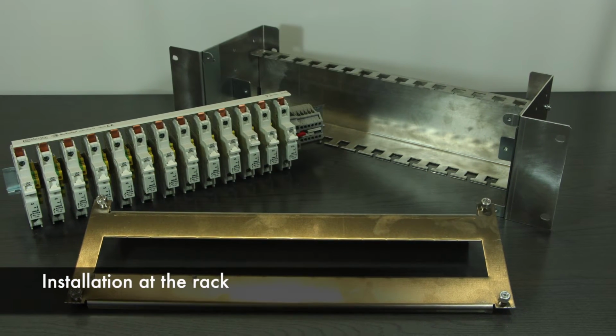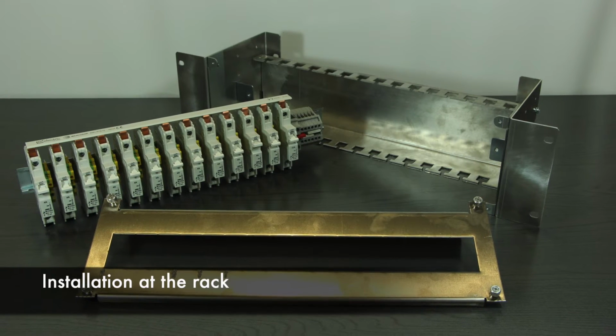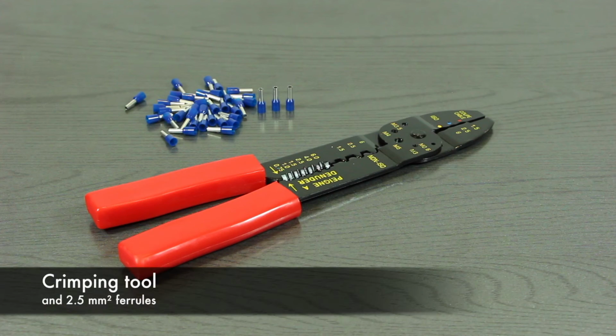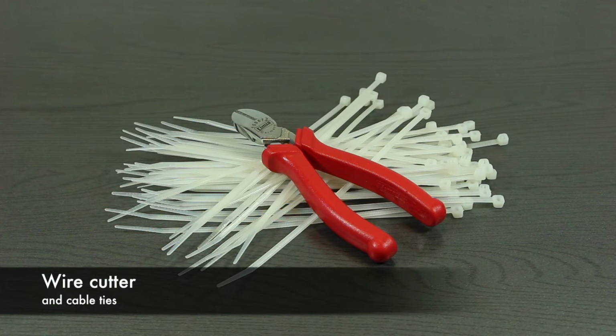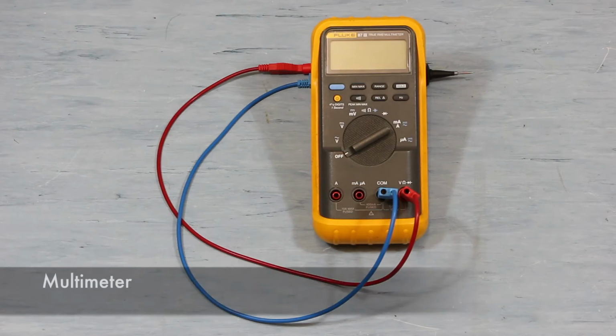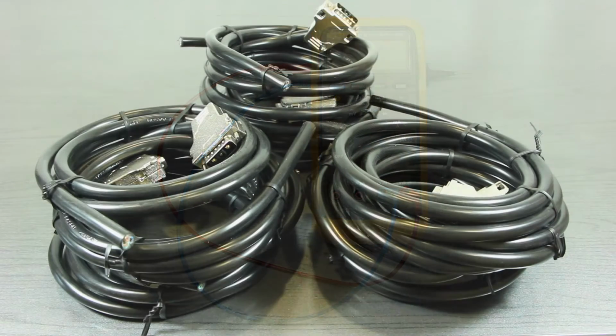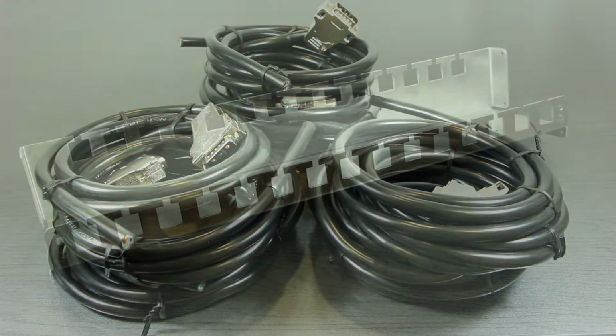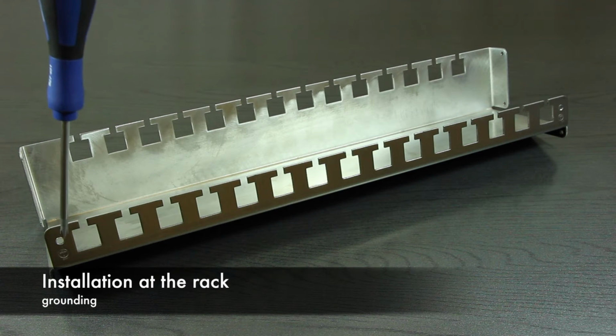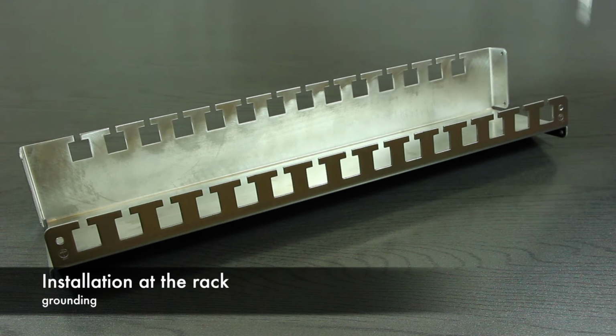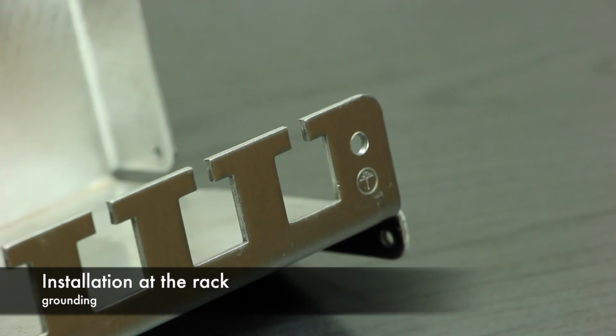The following tools will be required to install the power rail at the rack: the crimping tool and 2.5 square millimeters ferrules, the wire cutter and cable ties, the multimeter, and a set of power cables. Pay attention to the grounding. The cable guide has 2 grounding terminals which can be used if the rack is not grounded. The grounding is always mandatory.